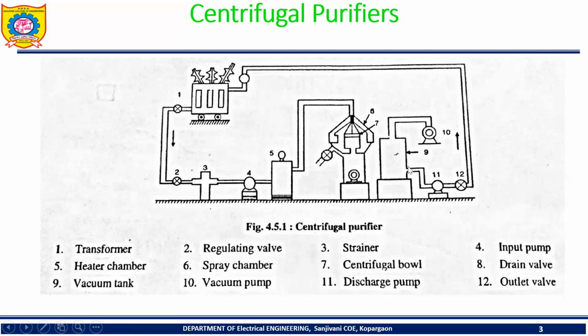As we know, the vacuum pump works at very low pressure as compared to atmospheric pressure, so we require a discharge pump. The discharge pump develops high pressure, which moves this transformer oil through this outlet valve and this pipe in the upward direction back into the transformer. So what are we getting? Filtered transformer oil. Are you getting?